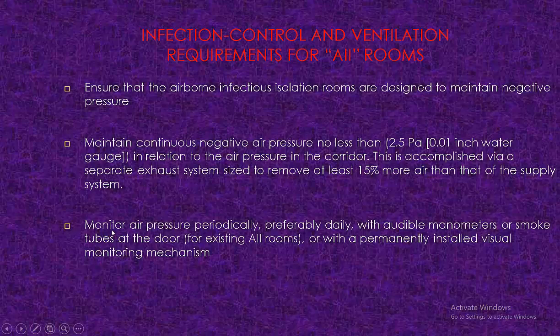The third is to monitor air pressure periodically, preferably daily, with audible manometers or smoke tubes at the door for existing AII rooms, or with a permanently installed visual monitoring mechanism. So we can monitor air pressure on a daily basis.